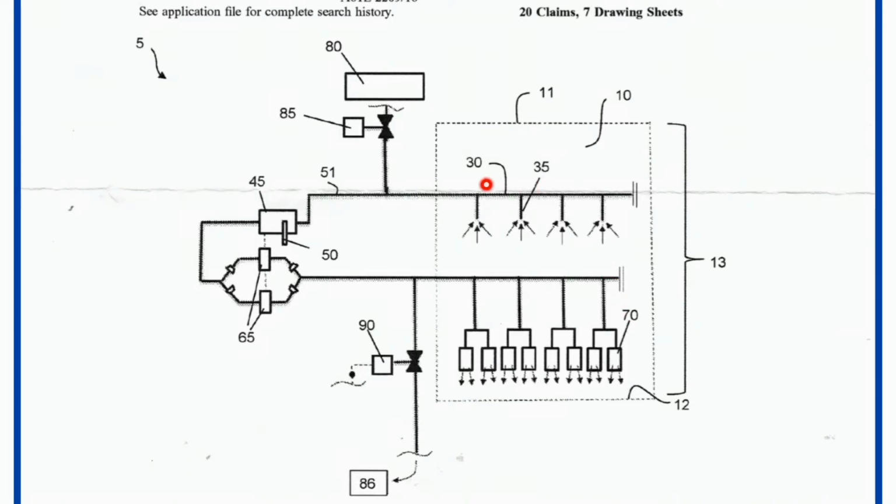We have a collection pipe overhead in the ceiling, and we have negative pressure on these nozzles. So that collection pipe sucks in the air that rises up. Instead of having turbulence blowing the air everywhere, in every direction, we have a net direction of air from floor to ceiling, okay? That gets rid of the spread of disease by turbulence.